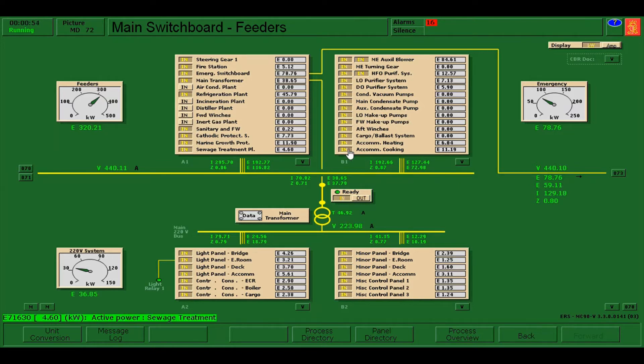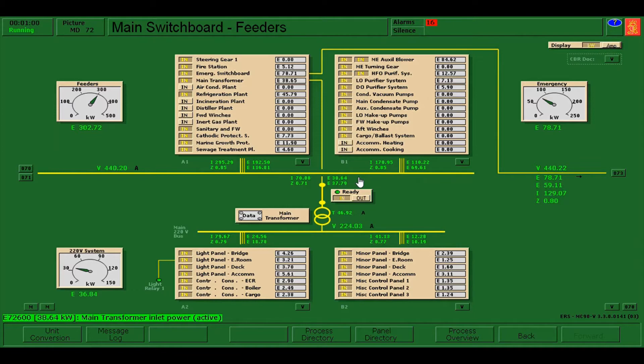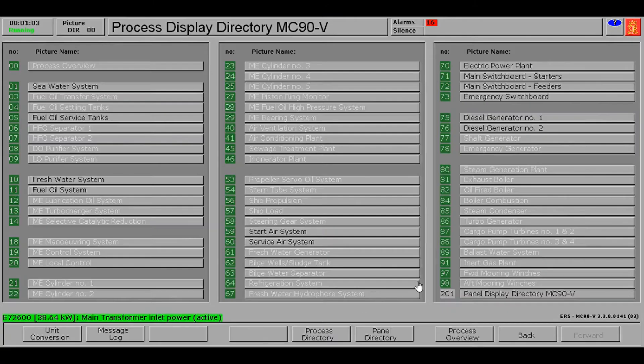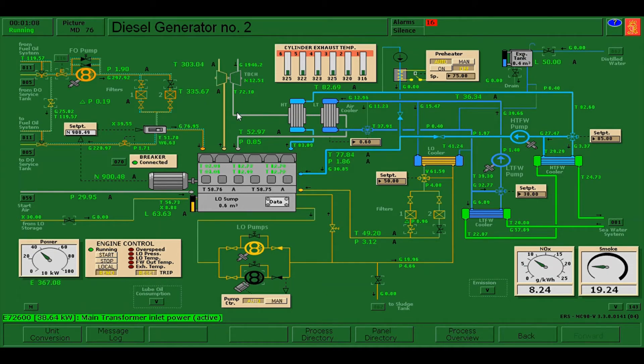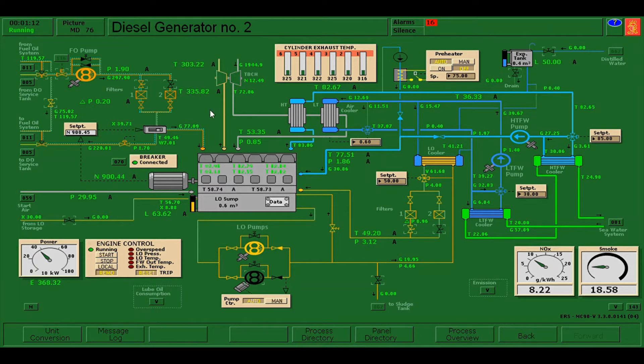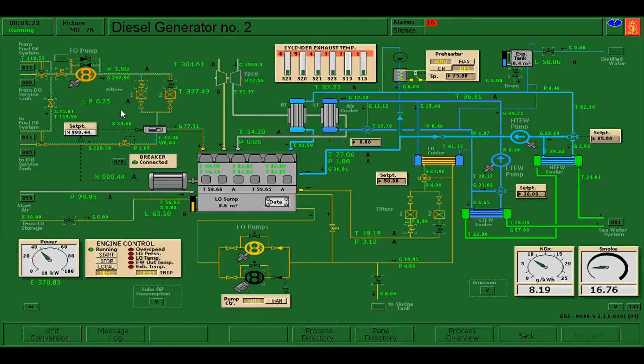Let's disconnect accommodation heating and cooking. I think this is enough. I'll go back to DG2. By the way, we need at least one minute of flushing as per the instruction, so it's already one minute past. We can now stop our diesel generator number two.